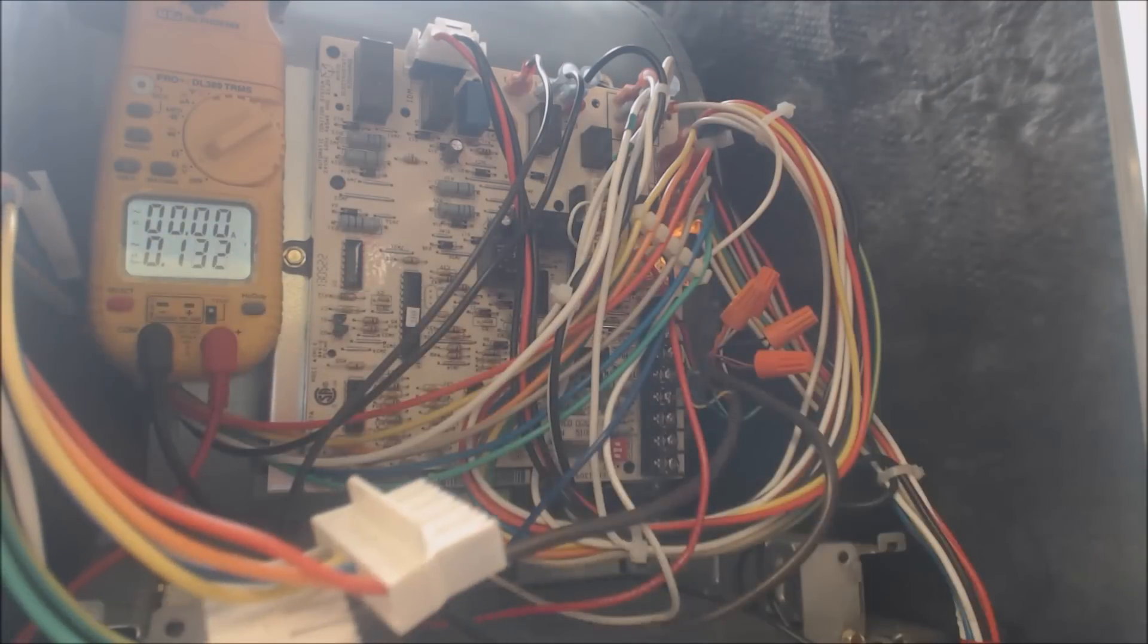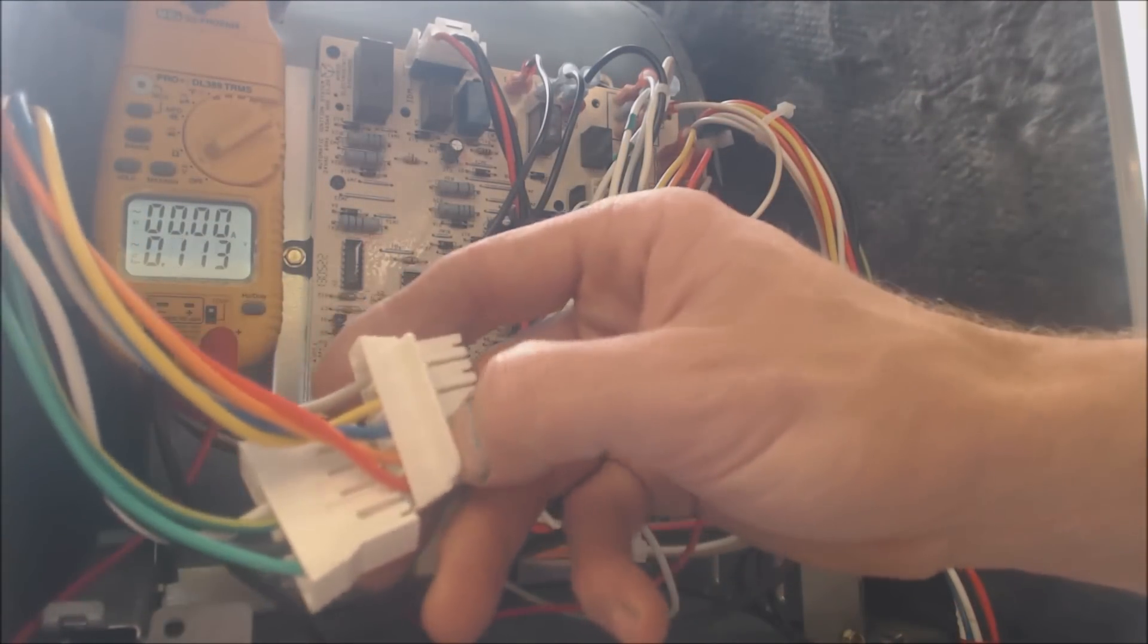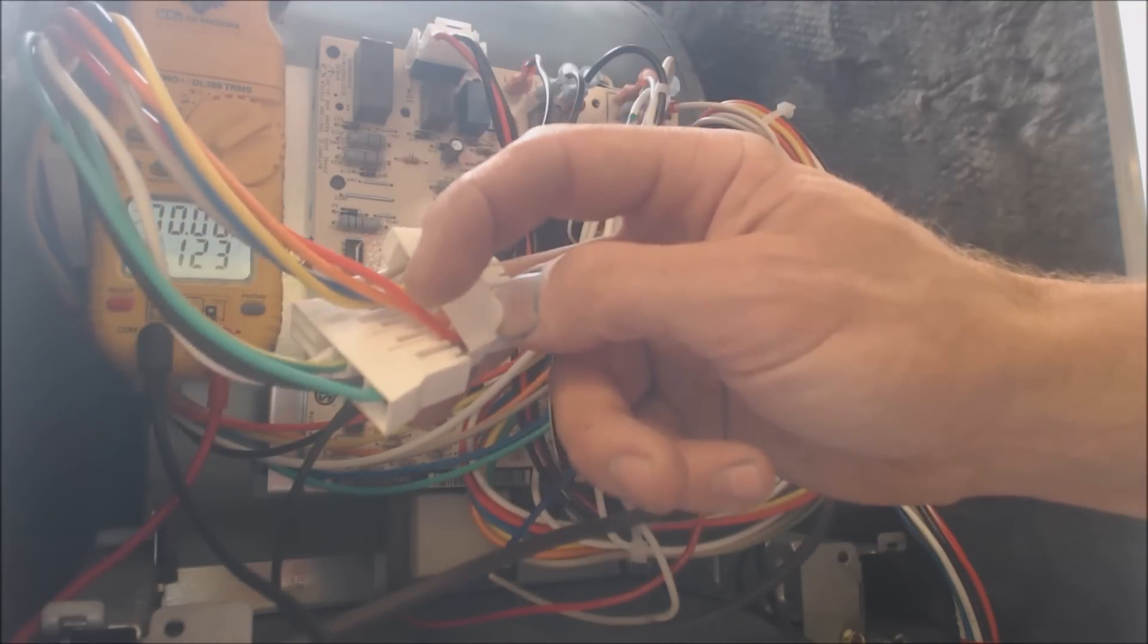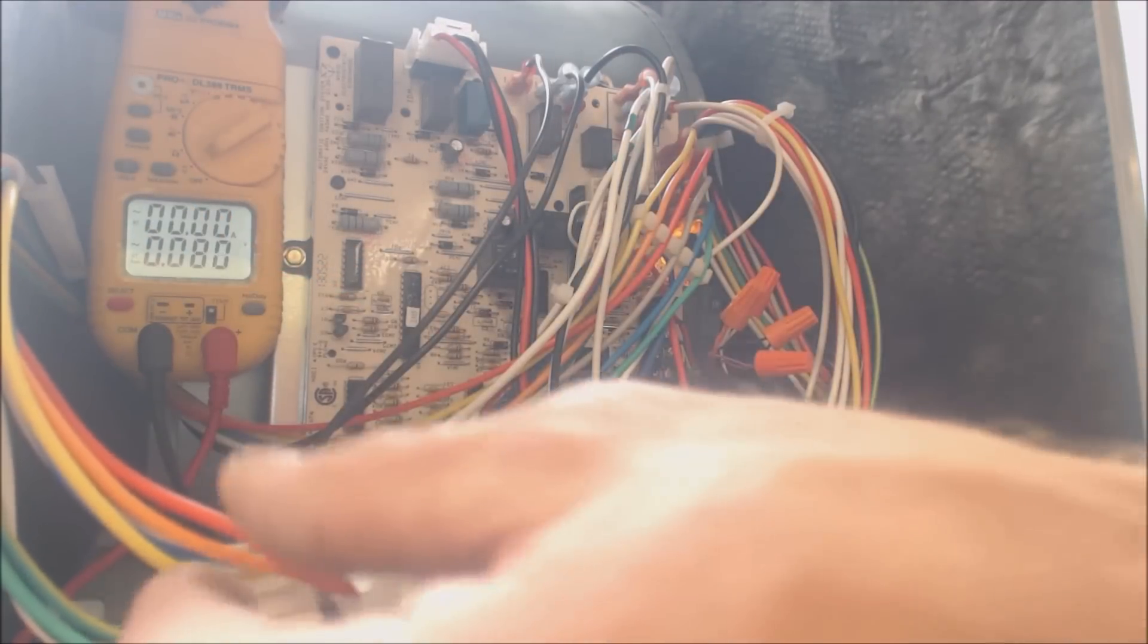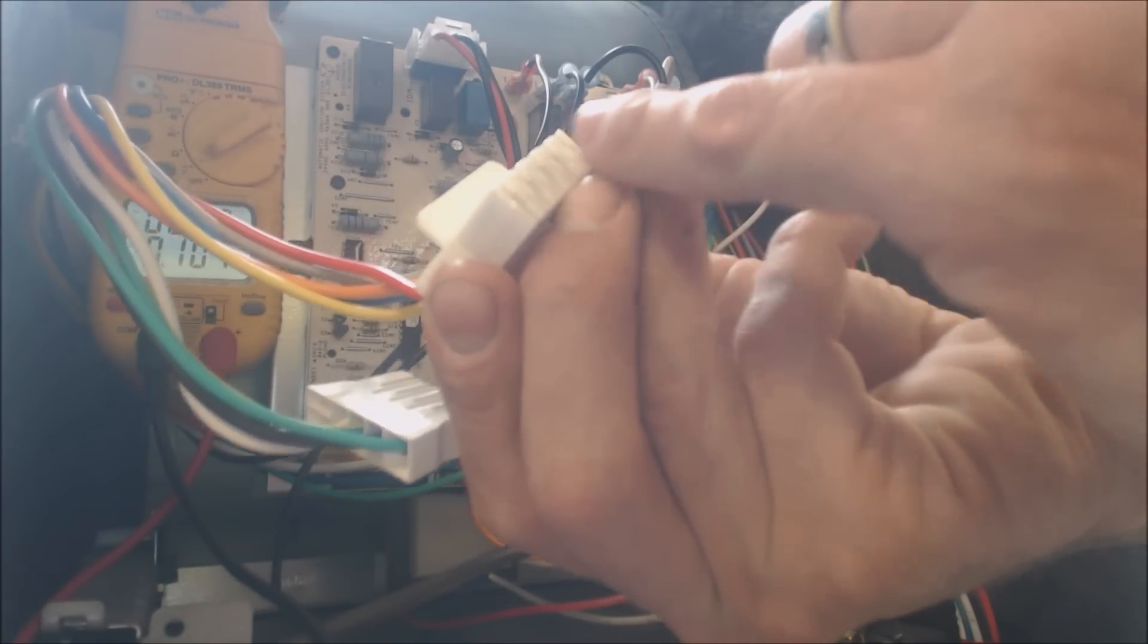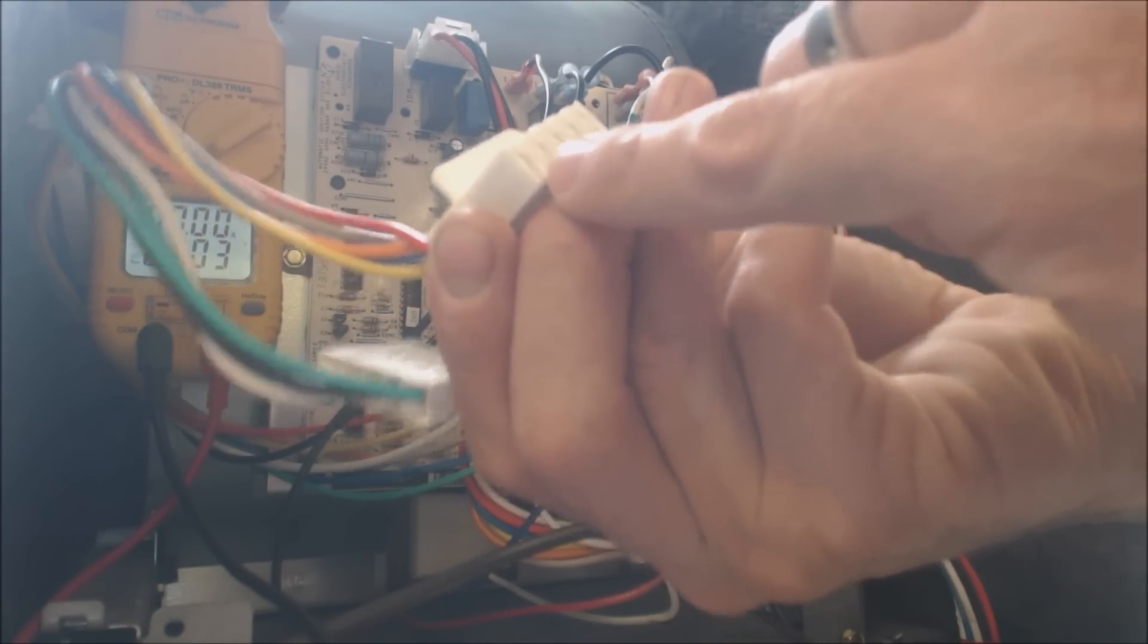Sometimes these wires are not pushed in all the way. So when you get to the job site, you turn the power off and you just go in and you just press each one of these wires in. Make sure they're making a good connection. Check over here. Make sure that these are not getting loose. They're just spade terminals.